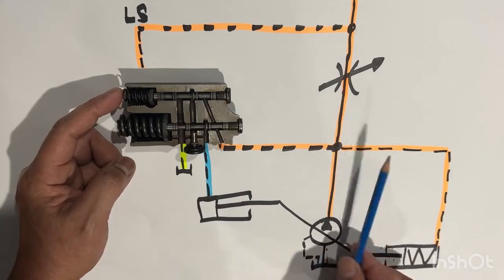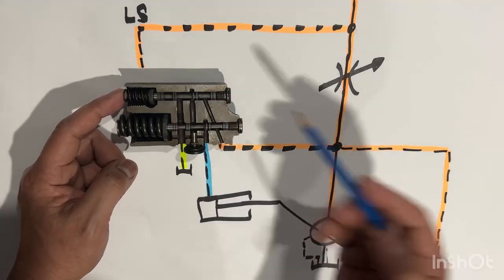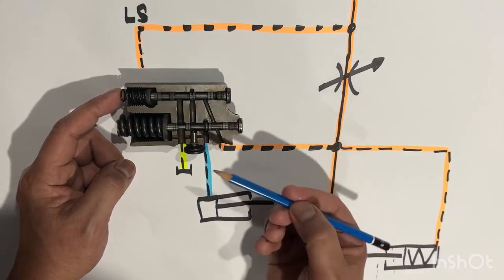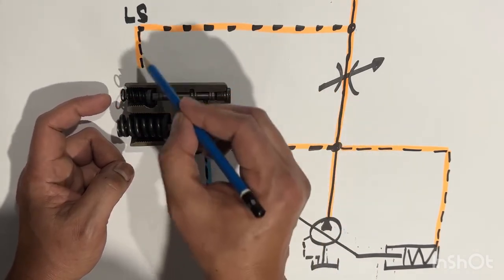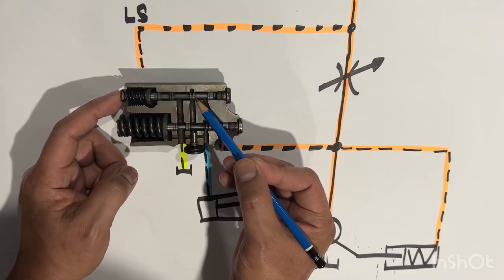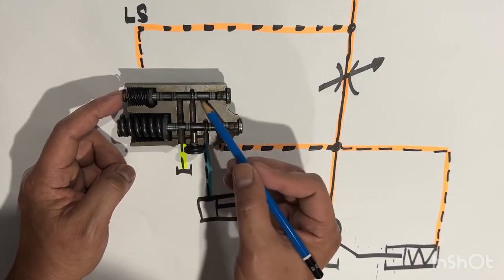Okay, and then the pump will stroke up. Okay, until such time the delta P is balanced, then this spool here will close. Alright, otherwise the pump will continue stroking. So this is the feedback. This load sense signal is a feedback. Okay, so this spool here is doing like that to balance, to maintain that delta P, whatever you set here. This time we set to 15 bar.